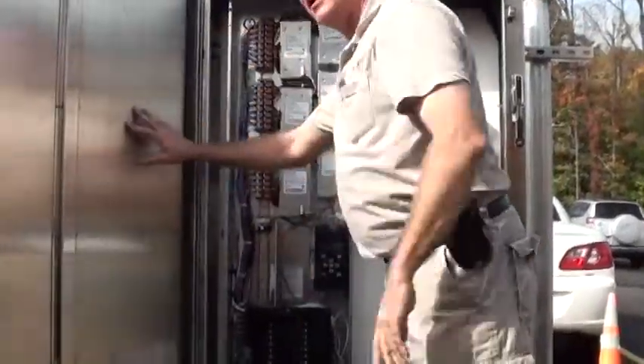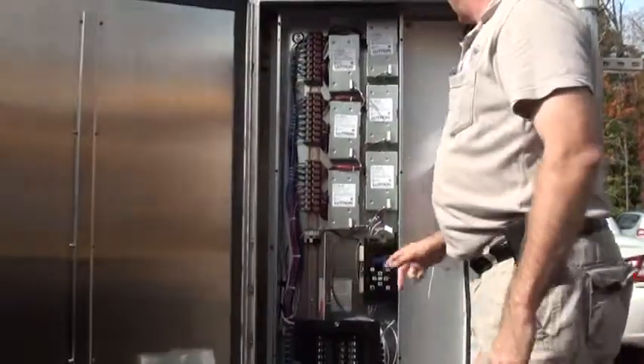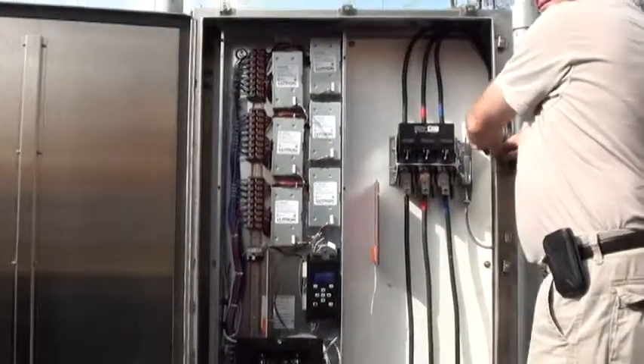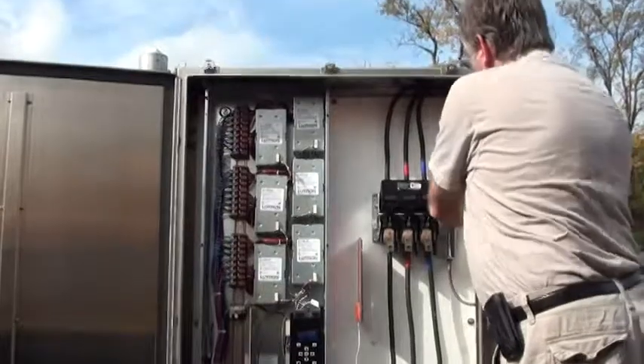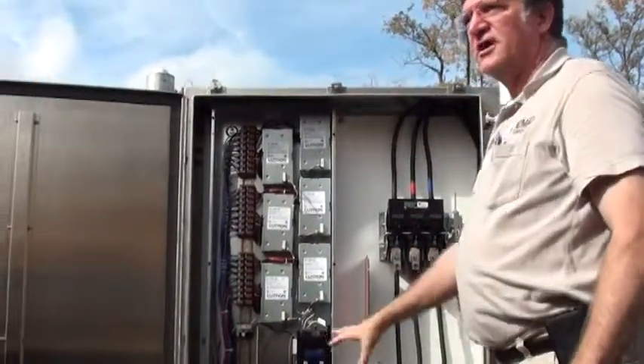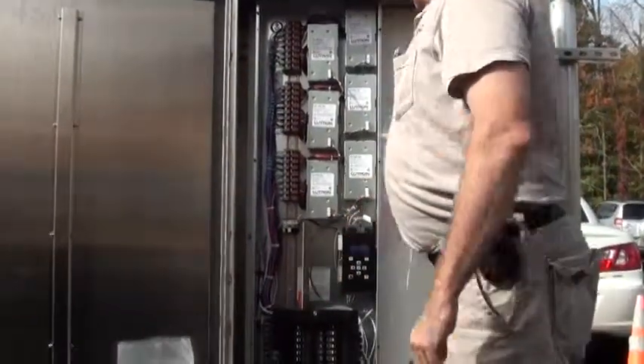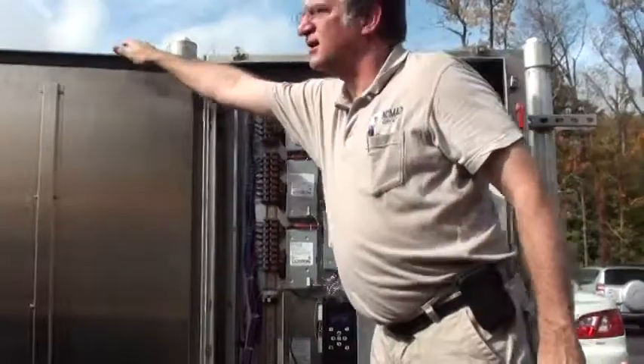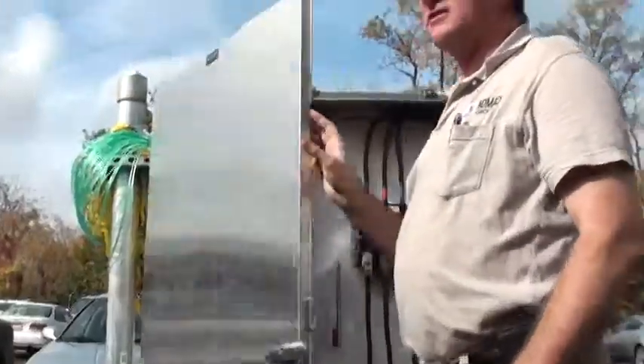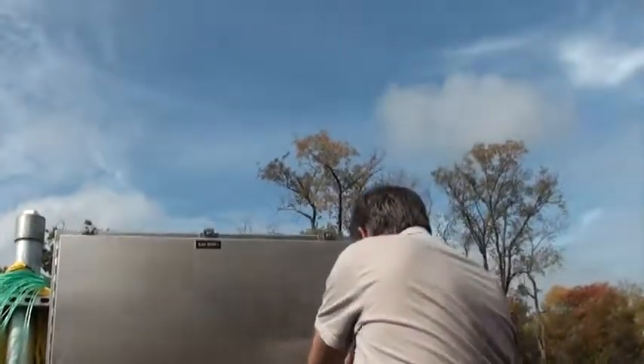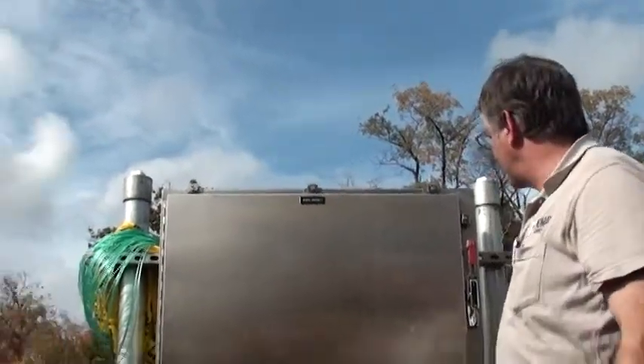So what you've got to do is pull the disconnect, open the door, but your power's off now, so you can't program. In order to get the power on, you have to hold the safety down, put your disconnect in to energize your units. Once energized like that, you can still leave that on when you close it back up, you don't have to turn it back off, and you're good to go. Just be very careful in there when you do that, because you have energized your electrical systems in there.